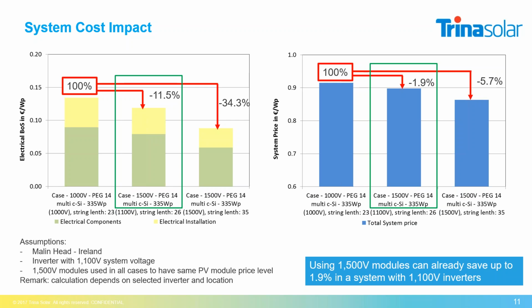If I go from a 1000 volt module to a 1500 volt module with the increased string lengths, you can see that the savings I have on the electrical BOS of 11.5% lead to a system price reduction of up to minus 1.9%, which is already a good reduction, because you can utilize the capabilities fully, and it's already a certain saving, especially under the very price-driven pressure we have in the solar industry. If you now compare it with a 1500 volt system, that means we also have an inverter capable of 1500 volts.